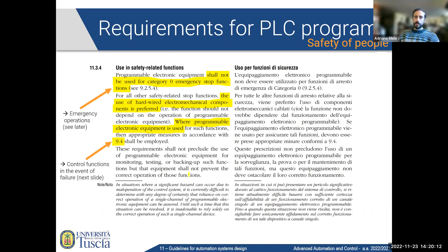What does that mean? It means that you can actually implement safety functions in your PLC or monitor that safety critical functions are performed correctly. But this should be a way of, let's say, reinforcing the safety measurements. So that should not be the main way of taking care of those aspects, but it can be an alternative way, or let's say an additional way, so that if for any reason the safety logic you have put into place, into action does not work, you also have the PLC helping that, but it's not the main way of taking care of these issues.